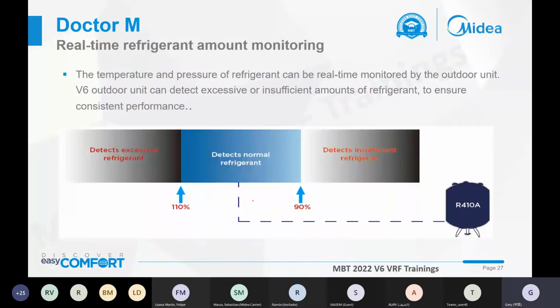And for the real-time refrigerant amount monitor, this function detects the temperature and the pressure of the refrigerant, so the outdoor unit's refrigerant can be monitored in real time.